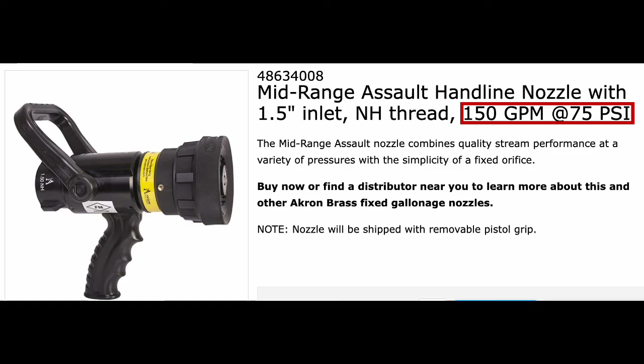If I had a big house fire and my water supply wasn't giving me enough pressure, my pump would still put out whatever pressure I told it to. So if there was less pressure coming into the pump than I was putting out, that becomes a negative pressure, a low pressure system. You're basically sucking water from the supply hose into the pump, which generates lower pressure. The pump works harder and spins faster, generating heat. That heat is absorbed by the water, and lowering the pressure lowers the boiling point. You'll quickly start to notice bubbles being drawn out of the fluid, and as soon as they hit a cooler temperature or higher pressure, they collapse. That collapsing of bubbles is called cavitation. This is a picture of an impeller from a pump damaged as a result of cavitation.